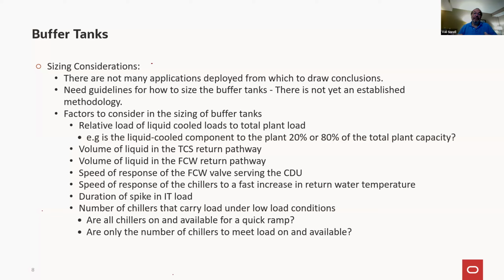That valve can go from mostly closed to complete open. It might take 30 to 60 seconds to do that. The speed of that response is really important also. And you have to look at the speed of response for that valve. And if you try to speed it up, it actually may hurt you because then you get more instability. The slower the response, the more stable the response. The faster the response, then you'll have up and down, and then you can actually miss the load completely. So that becomes a factor.